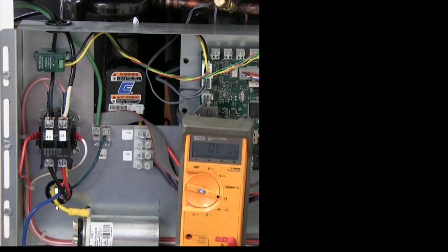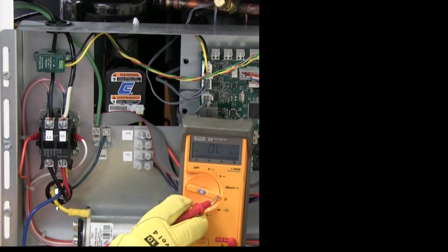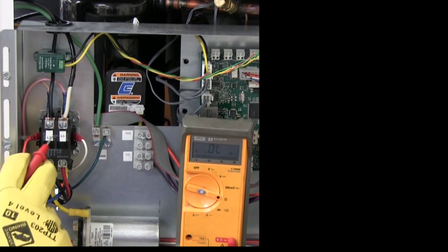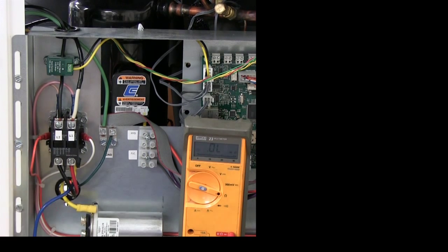In order to test the run capacitor, we'll use a multimeter set to the resistance function. The important key is to make sure that power is disconnected from the unit. I've already done so, checking to make sure there's no voltage between L1 and L2.